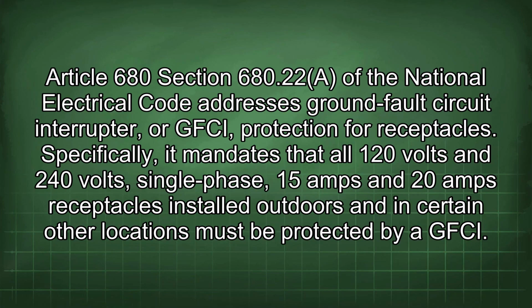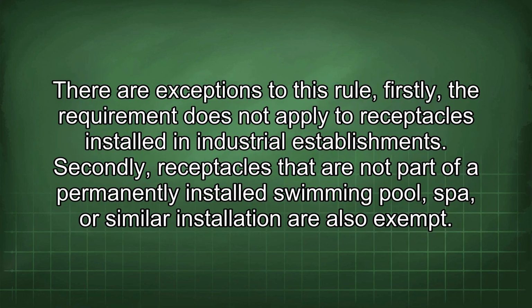Article 680 Section 680.22 of the National Electrical Code addresses ground fault circuit interrupter, or GFCI, protection for receptacles. Specifically, it mandates that all 120 volts and 240 volts single-phase 15 amps and 20 amps receptacles installed outdoors and in certain other locations must be protected by a GFCI. There are exceptions to this rule.